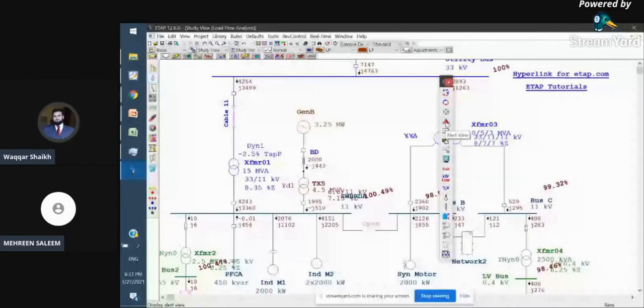For example, if I run this simulation and find that the generator has turned red, it means the generator is overloaded, or it is suffering from excess reactive power provision to the network, or excess reactive power absorption from the network. At that time, we have to investigate the problem and find a solution. So the alert view option lets you see the different possible hazards or critical alerts in the network after simulations are run.